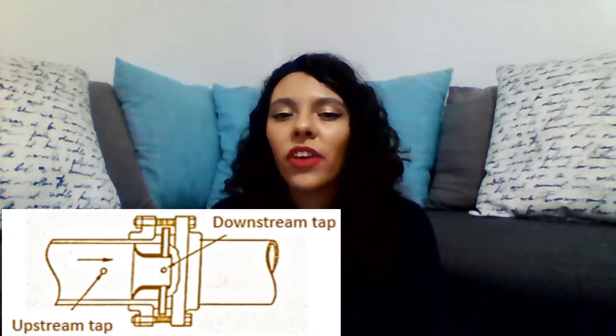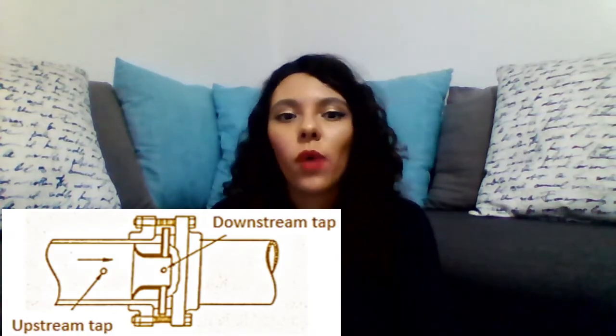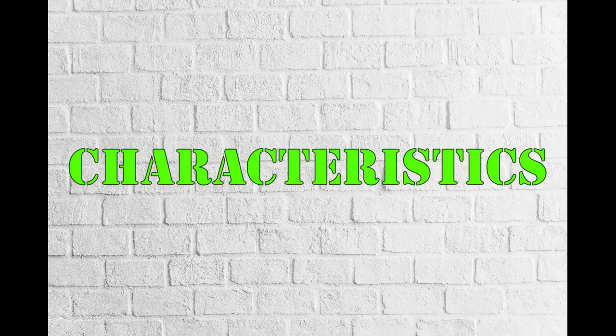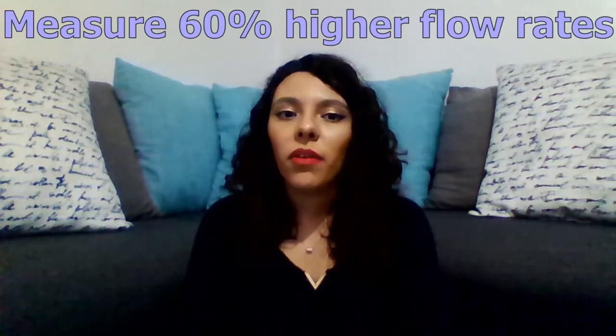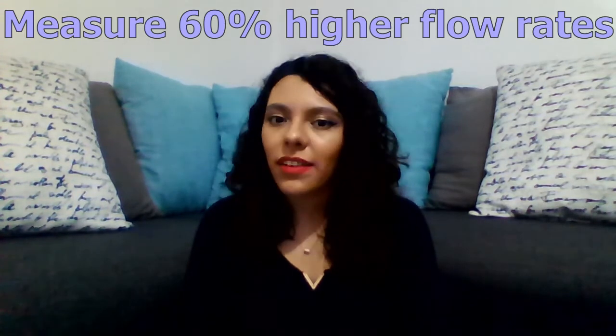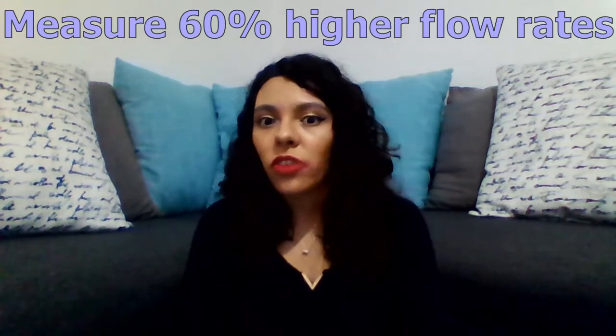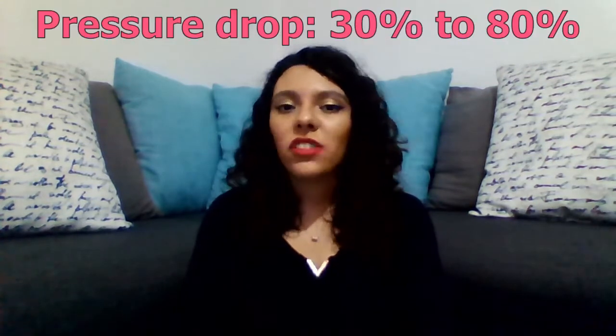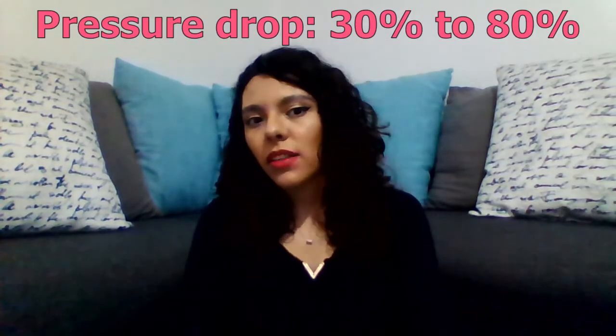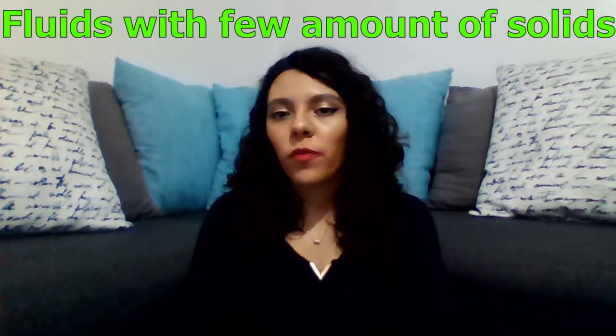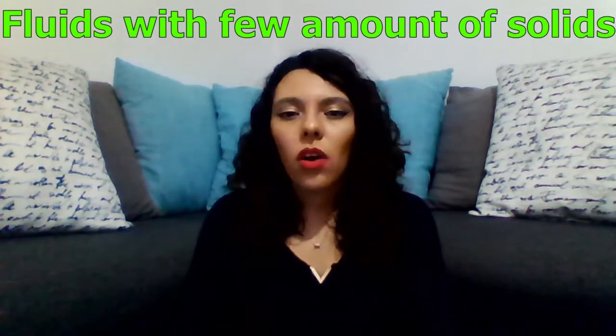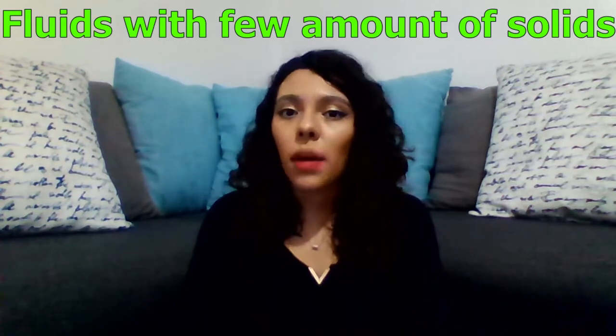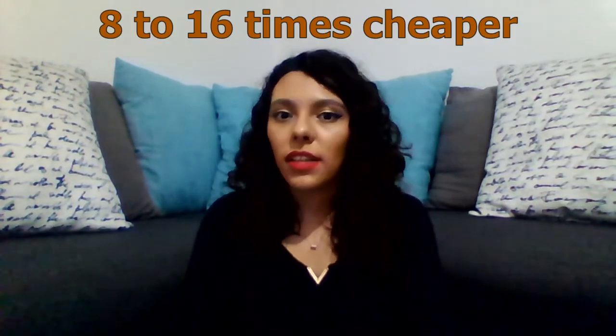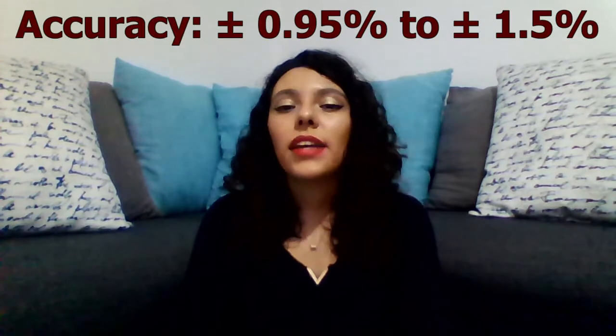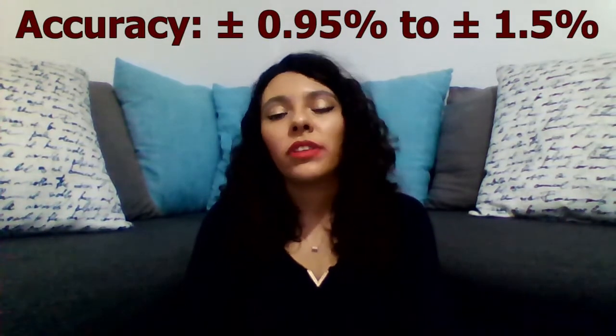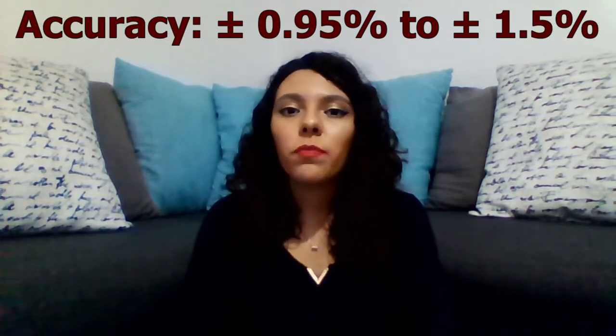The nozzles are located in the pipe with a previous tap and one in the center of the smaller section. They are capable of measuring flow rates 60% higher than those of the orifice plates under the same operating conditions. Its pressure drop is 30 to 80% of the differential pressure. They can be used for fluids that carry a small amount of solids, although if these are abrasive, they can damage their precision. They are 8 to 16 times cheaper than the orifice plates and have an accuracy of ±0.95% to ±1.5%.